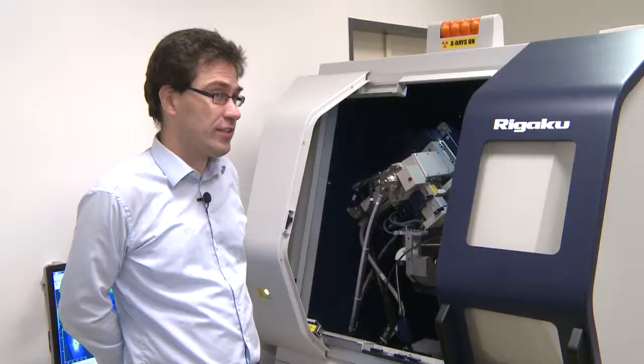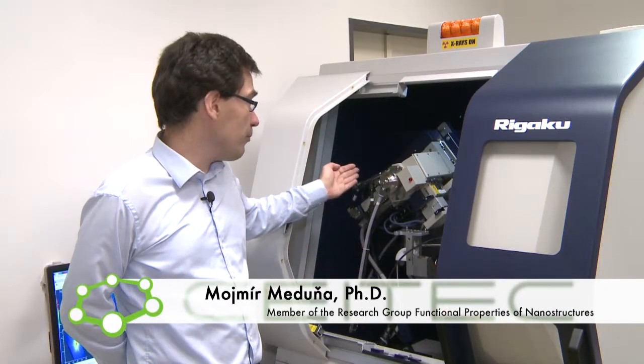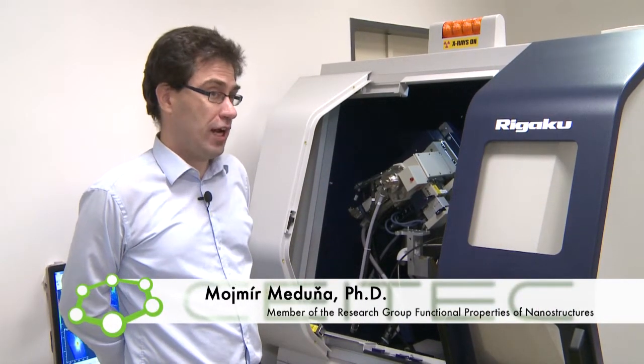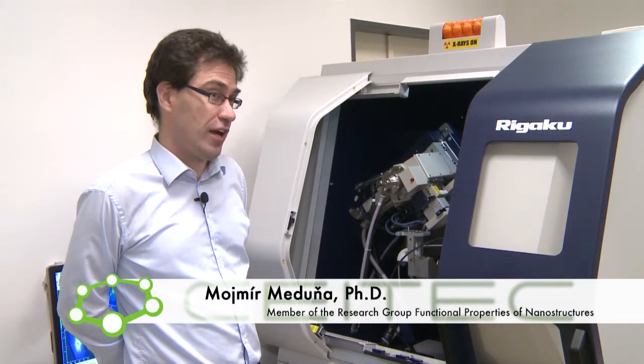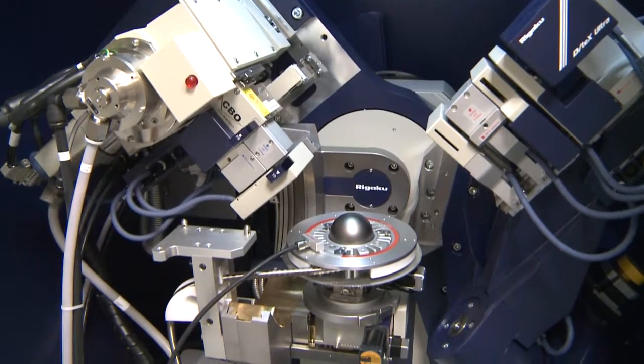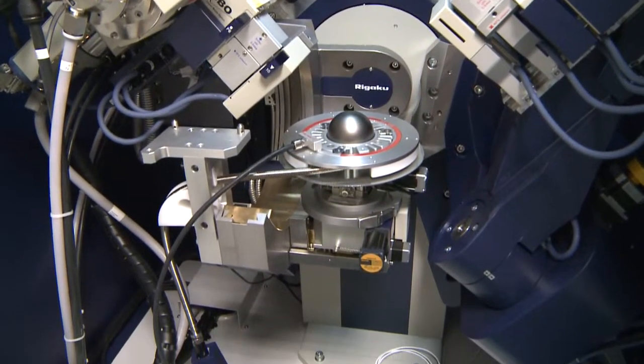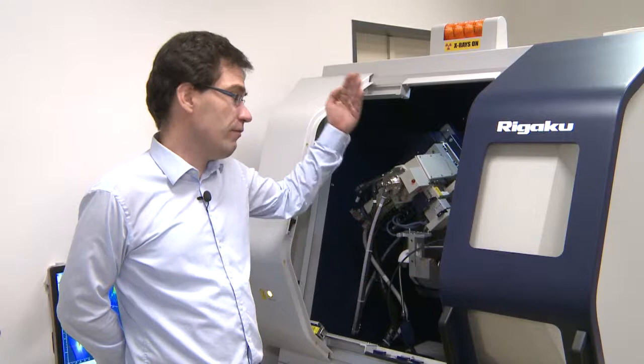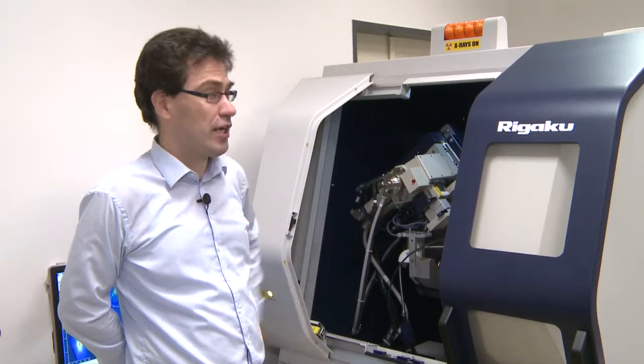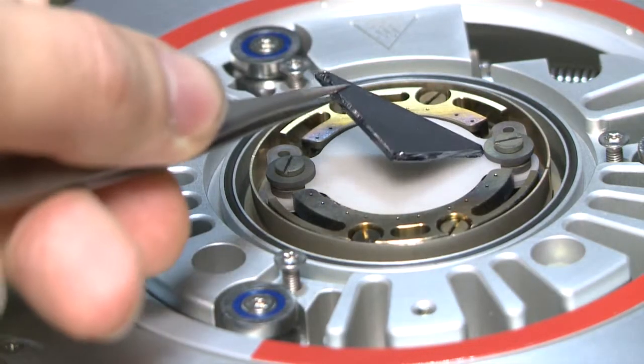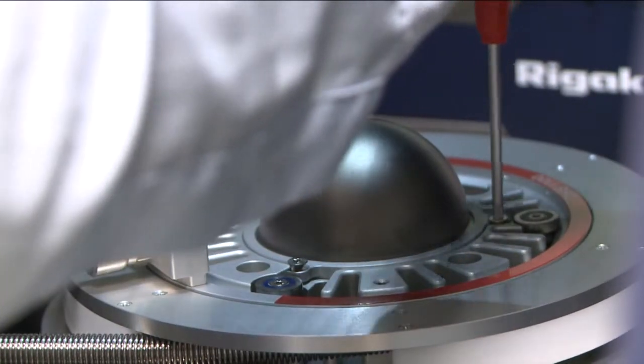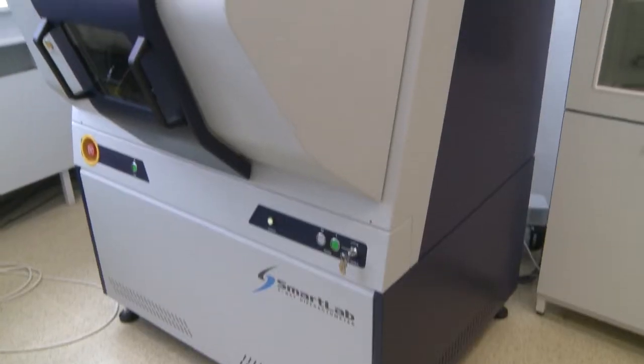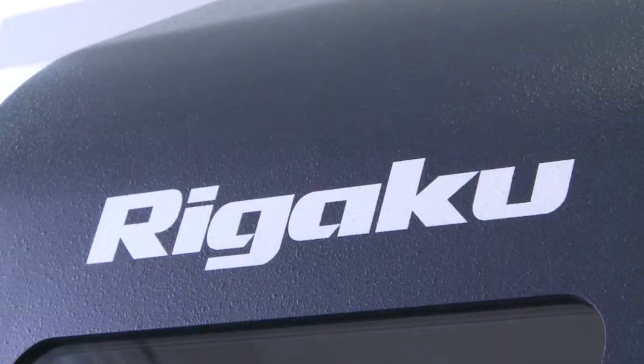The diffractometer for measuring thin layers has at its disposal an X-ray lamp with a rotating Cu anode, which enables it to achieve up to 3 times more power than a standard diffractometer. The arm of the diffractometer is able to move not only in a vertical direction, but also in a horizontal direction, which allows us to measure the distribution of intensity scattered from the sample in more detail.